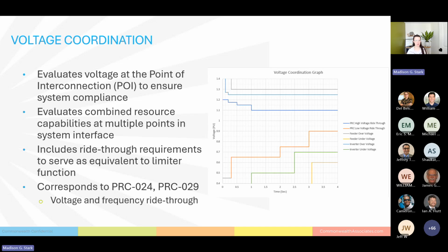So the first thing we're going to touch on is voltage coordination. So voltage coordination when you're doing distributed type generation, so you have multiple PV arrays that are connected at one point of interconnection or POI, you generally are evaluating the voltage at the POI and then backtracking it through the system to test the inverter capabilities. So what does this look like as far as actual coordination? Similarly to a synchronous generator, you're going to start in this middle at this 1 per unit voltage. This is your baseline ideal operating conditions. And then you kind of work your way out.